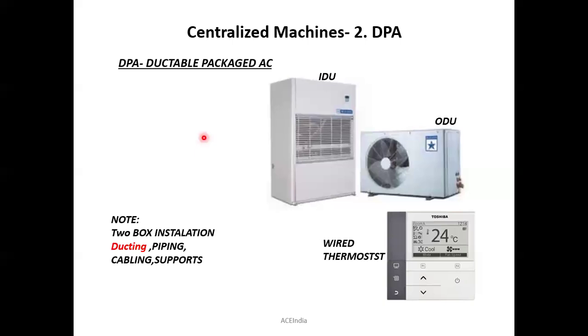All right. Next is our DPA, which is a ductable packaged AC, or vertical unit. Typically, a ductable packaged air conditioning system is a floor-mounted unit, and it is also a split kind of mechanism, which means you will have an indoor unit and an outdoor unit, and the other connections are the same, which means the wired thermostat connection, and ducting will also be there. But here, in order to install this indoor unit, typically you need some kind of space. Why? Because I told you this is a floor-mounted unit.